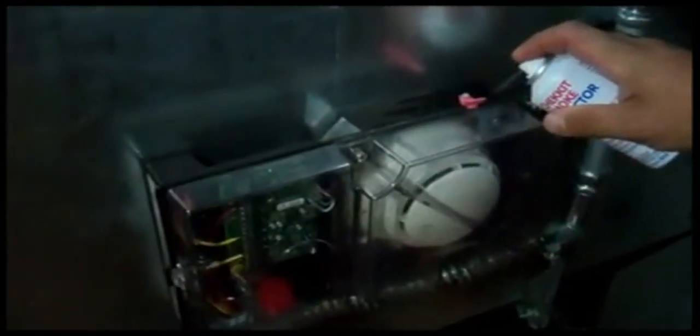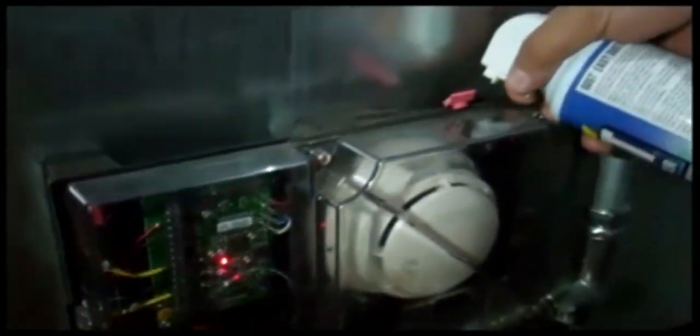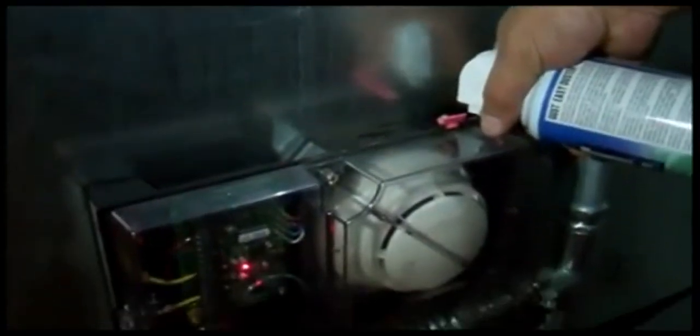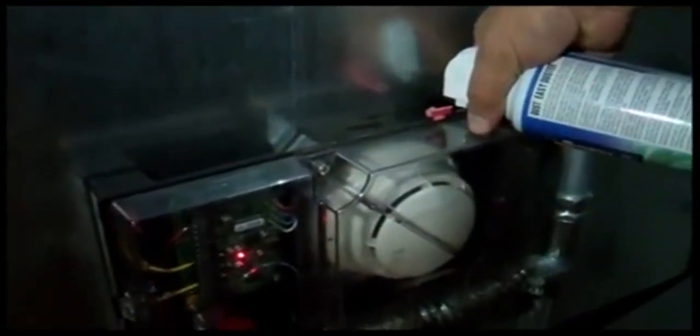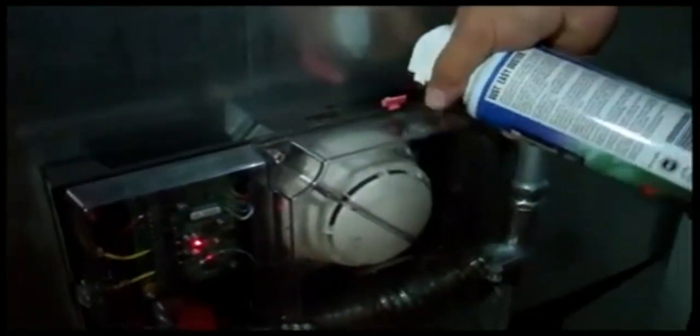Once the airflow is verified, the device is tested using an aerosol smoke solution to verify that the device will activate when the smoke enters the chamber. Once the activation is verified, the chamber of the device is then cleared from smoke using compressed air.